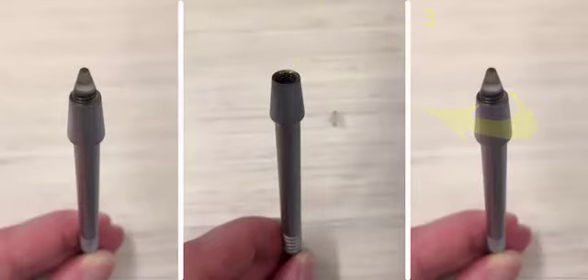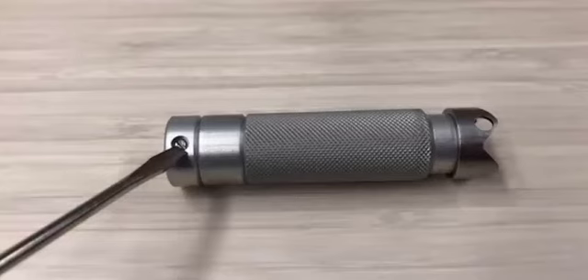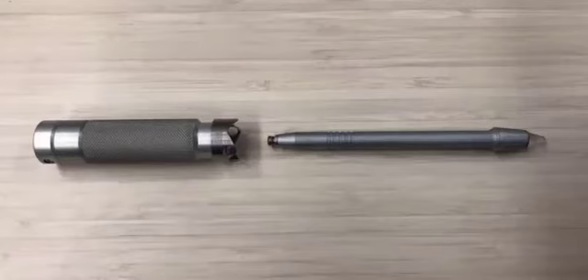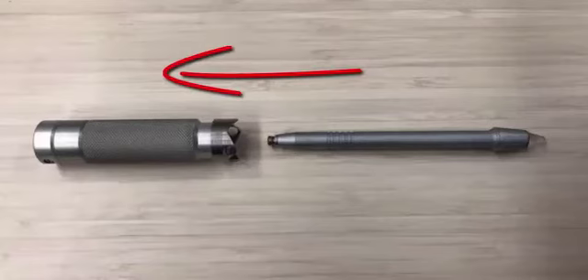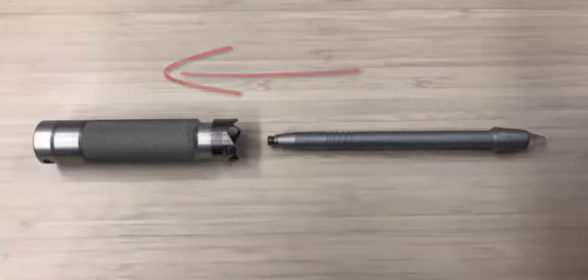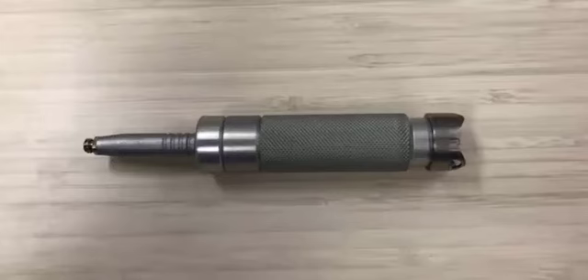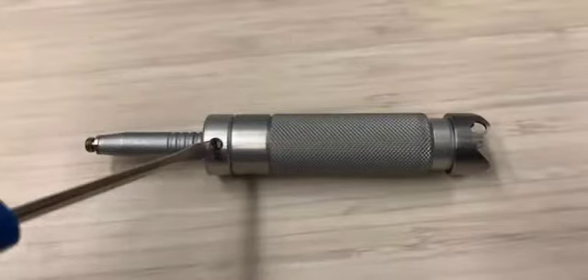We can now set up the spring-loaded holder. The first step would be to loosen the set screw on the spring-loaded holder using a flathead screwdriver. We can then insert the microdot end of the V260 into the V-notch side of the spring-loaded holder until it cannot be inserted any further. Then we will use the flathead screwdriver to tighten the set screw so it holds the transducer securely.